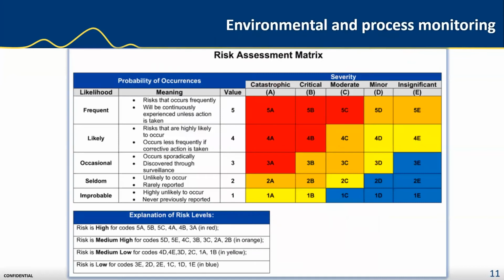So these risk assessments should be conducted based on detailed knowledge of the process inputs and final product, the facility, equipment, the criticality of specific processes and steps, the operations involved, the routine monitoring data, the monitoring data obtained during qualification, and knowledge of typical microbial flora isolated from the environment. The risk assessment should include the determination of critical monitoring locations, those locations where the presence of microorganisms during processing may have an impact upon product quality, for example, in your grade A aseptic processing areas and the grade B areas that directly interface with the grade A areas, etc.